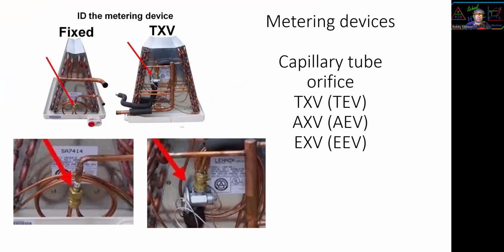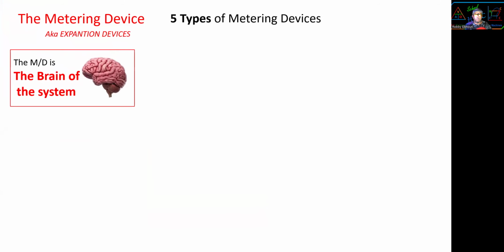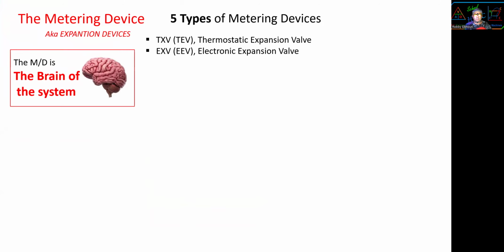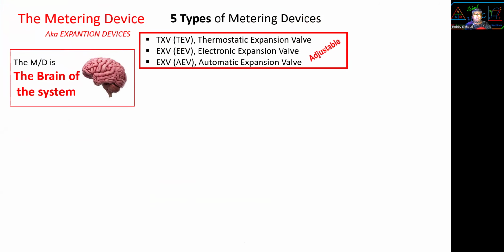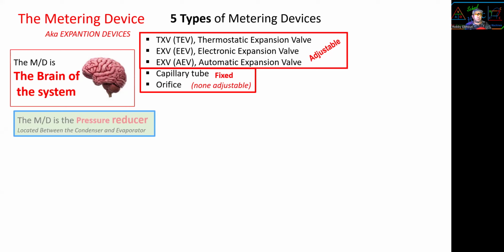Alrighty. Metering devices: we have the cap tube, orifice, thermostatic, automatic, and electronic expansion valves. And we have the fixed orifice and fixed metering device and the adjustable metering device. The metering device is also called an expansion device. It is the brain of the system. We have five types: thermostatic expansion valve, electronic expansion valve, and automatic expansion valve, which are adjustable. We also have the fixed, non-adjustable ones, the capillary tube and the orifice.